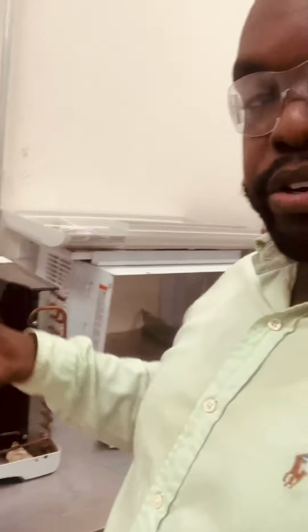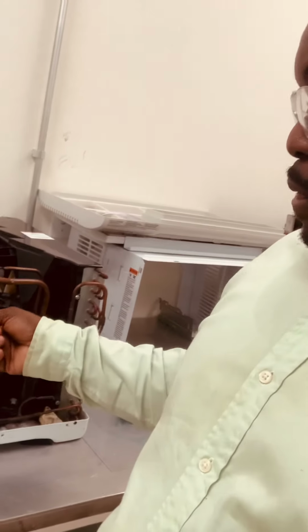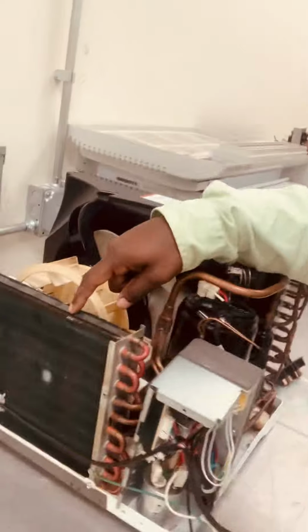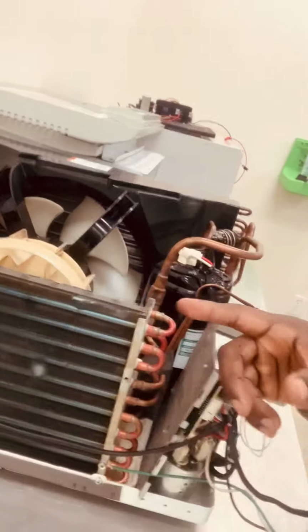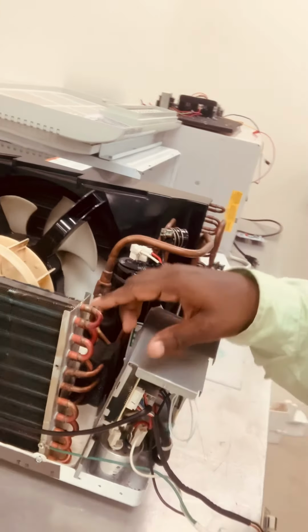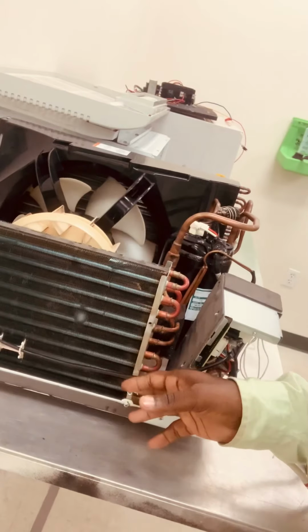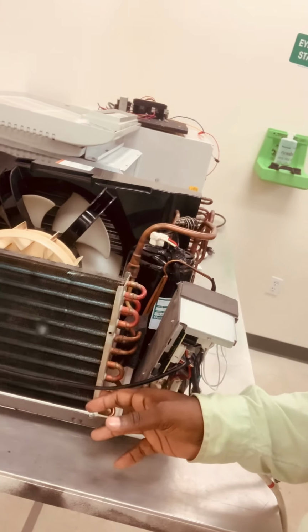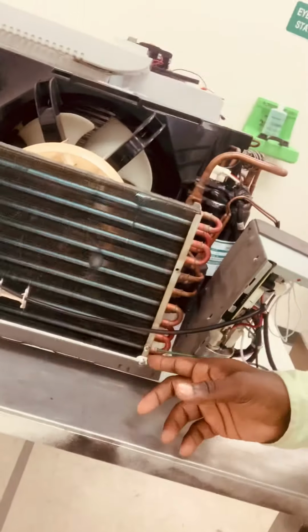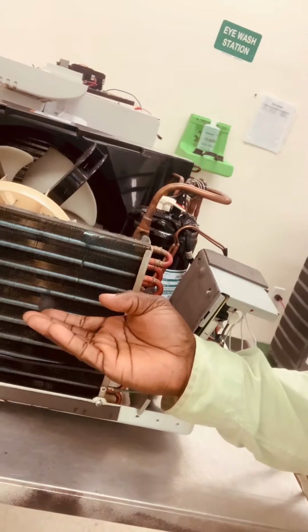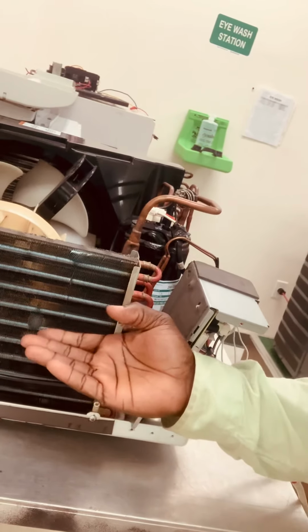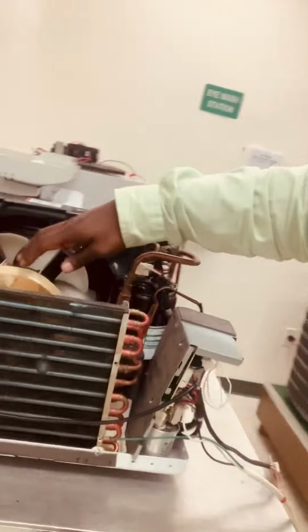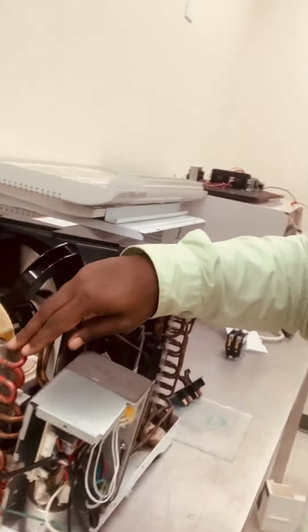It goes into your metering device here. It dramatically drops the pressure and drops the temperature. And then it goes into your evaporator. With the aid of the fan motor, the evaporator's sole purpose is to absorb the heat. At the bottom of the coil is going to be a saturated 75% liquid, 25% vapor. By the time it gets midway of the evaporator coil, it's going to be saturated 50-50, 50% liquid, 50% vapor. When it leaves your evaporator coil, it's going to be 100% superheat.